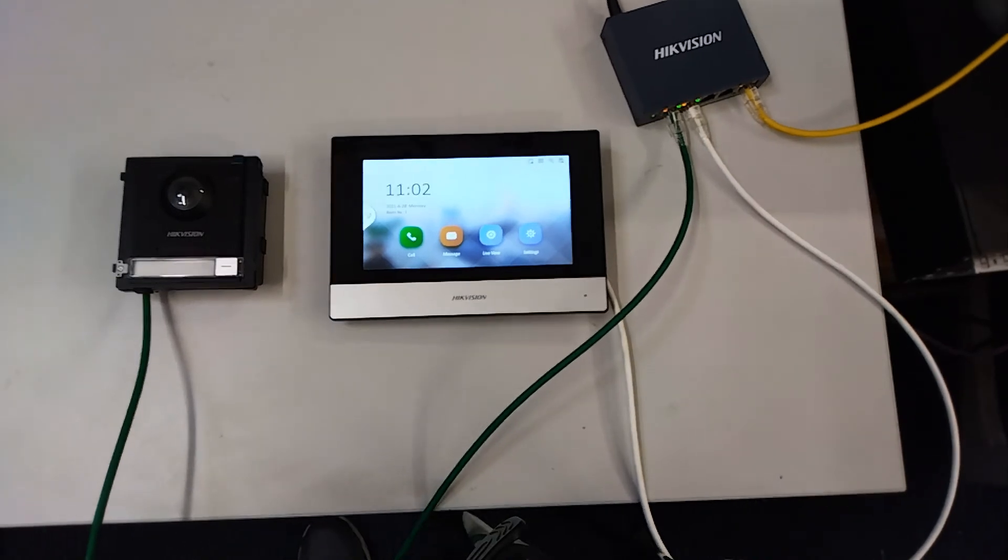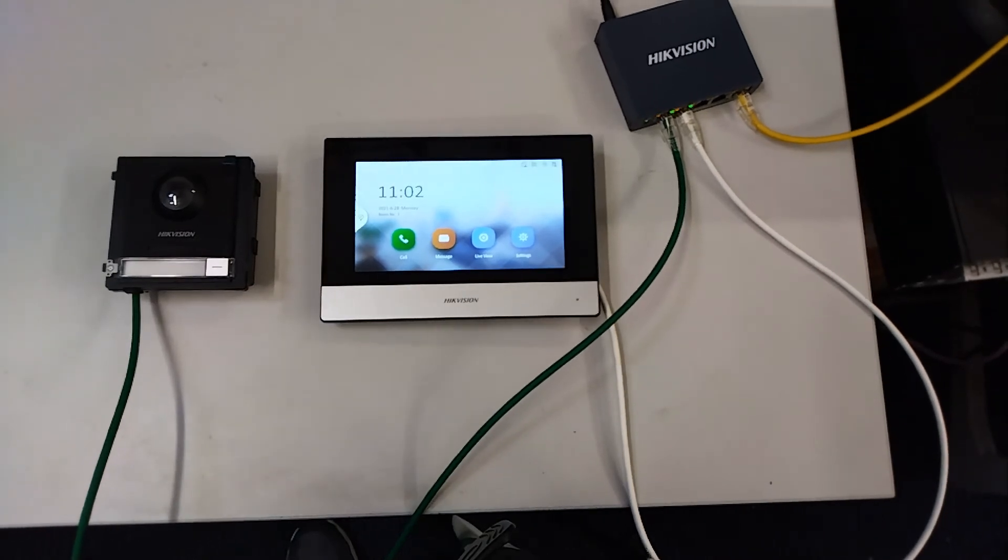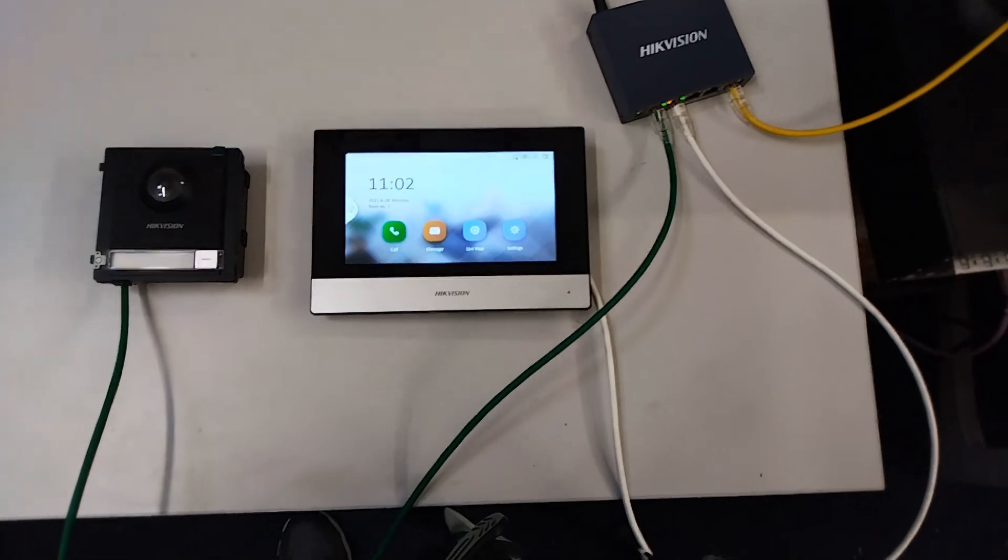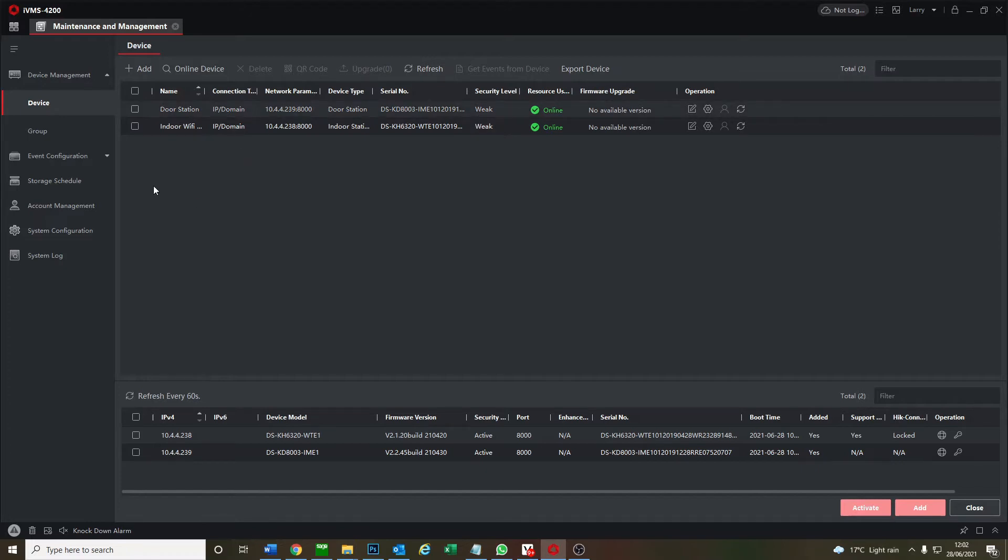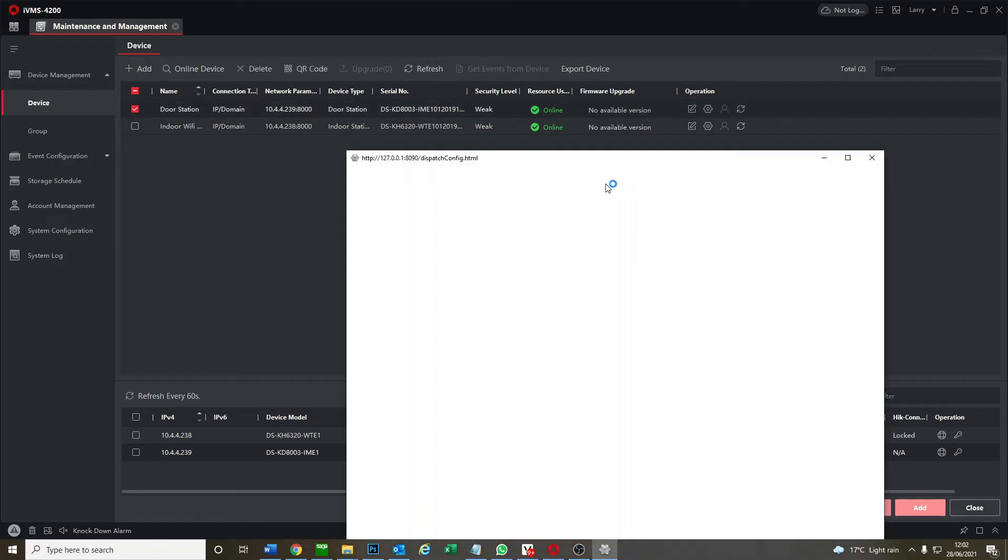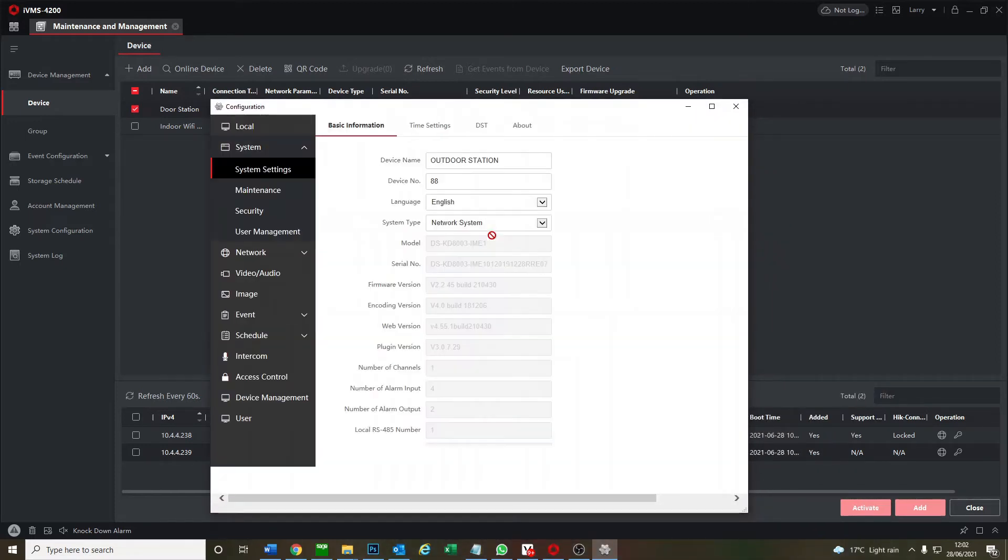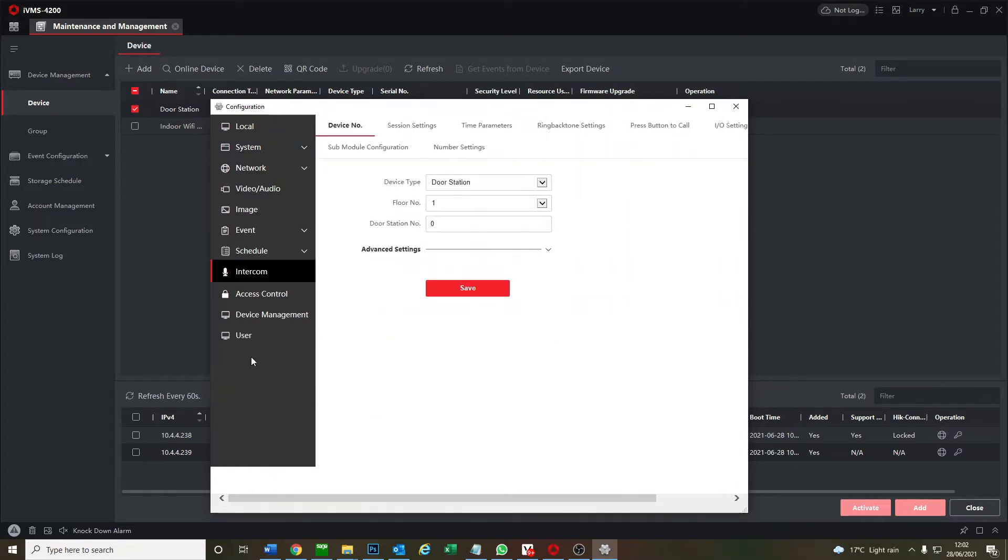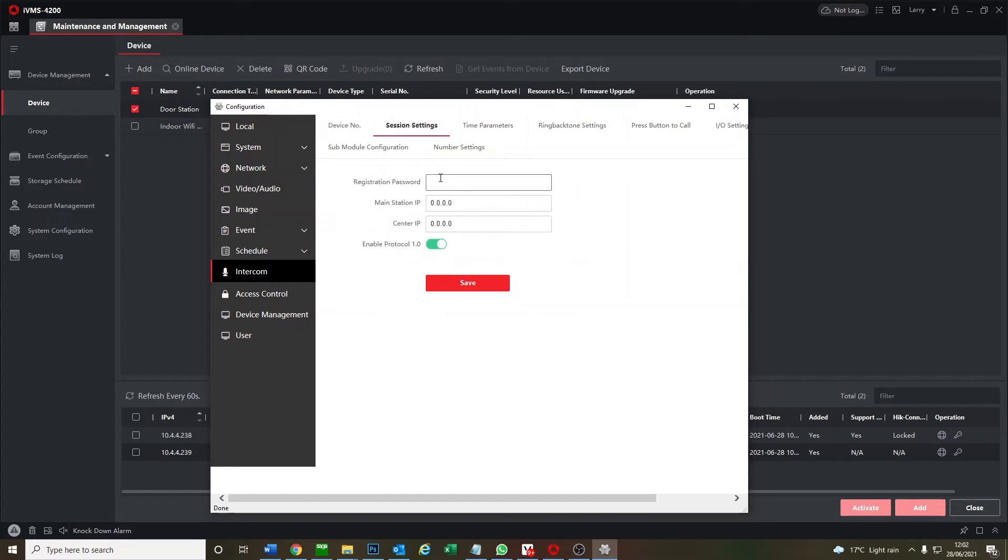We're on IVMS, our devices are online, activated, enable DHCP. Please check out previous videos if you haven't done that. Now we'll set it up. This is our door station. We're going to click on the cog icon and quickly configure this. We go to intercom, session settings. All we have to do here is put in our password. We save that. Save succeeded.